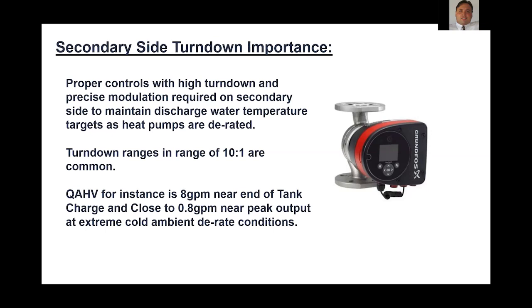And then at really cold ambient conditions where the equipment's derated, in order to maintain those discharge water temps, to maintain that thermocline and that storage temperature that you're trying to achieve on the tanks, you could see water flow rates down to 0.8 GPM or even possibly lower when you get down to that minus 35 level that Mike mentioned. So you're dealing with turn down ranges in the range of 10 to 1, if not higher at times. So it's paramount to have proper controls in place, proper pumps that can actually handle that degree of turn down. This is really almost like process level water flow modulation requirements.